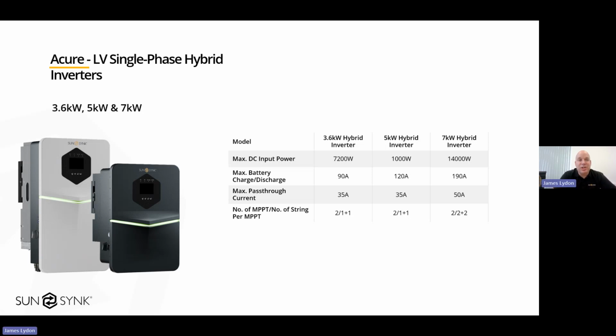Okay, so the low voltage single phase Acure, we will be doing a 3.6, a 5, and a 7. In Ireland, it's predominantly going to be the 5 kilowatt. On the previous slide, we saw the 100% PV oversizing. On all of the Acure models, you can connect double the amount of PV over the rated value of the inverter. So on the 5 kilowatt Acure, you can connect 10 kilowatt of PV into it.